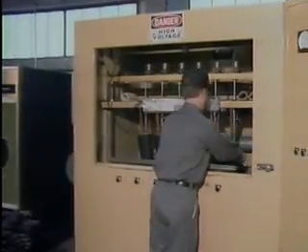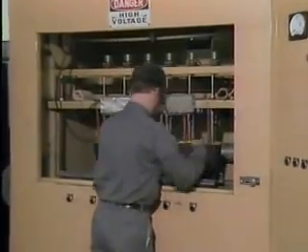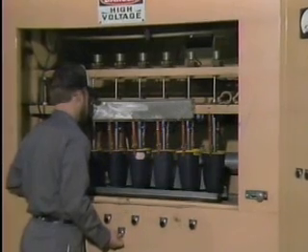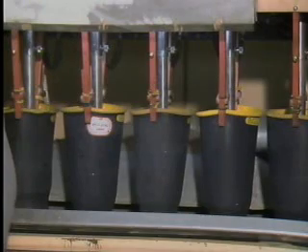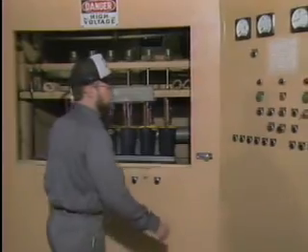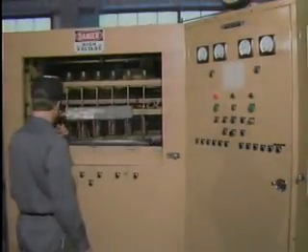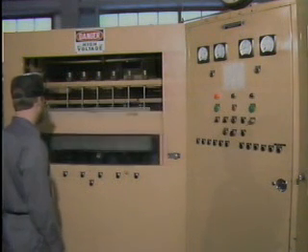This is a test apparatus that's used to perform dielectric tests on insulating gear. The apparatus can test 6 gloves at a time. Each glove that's being tested is first filled with water and then lowered into a water-filled tank in the apparatus, which is connected to ground. A hot lead then applies the test voltage to the water inside the gloves.